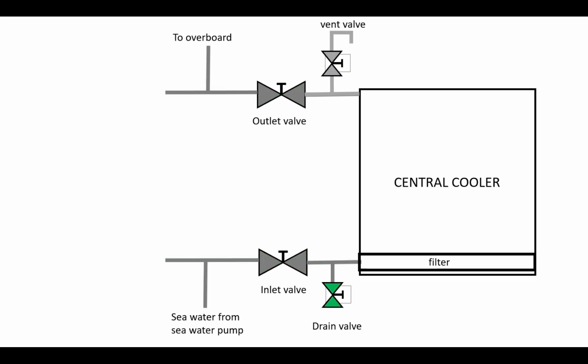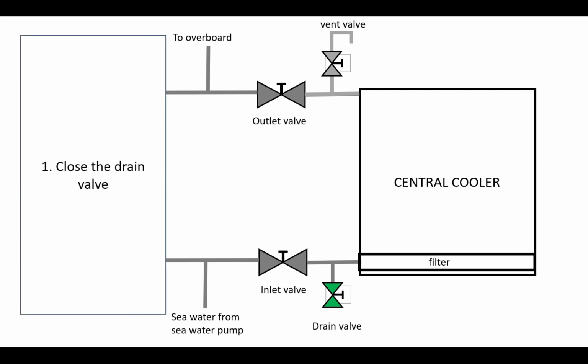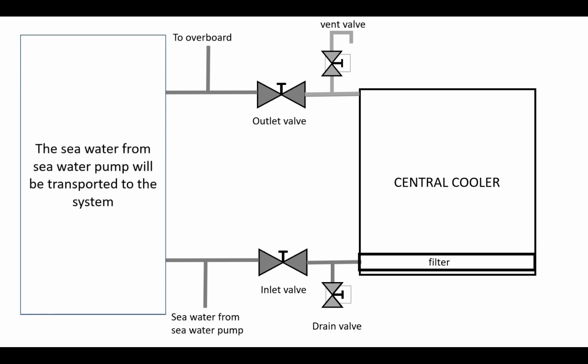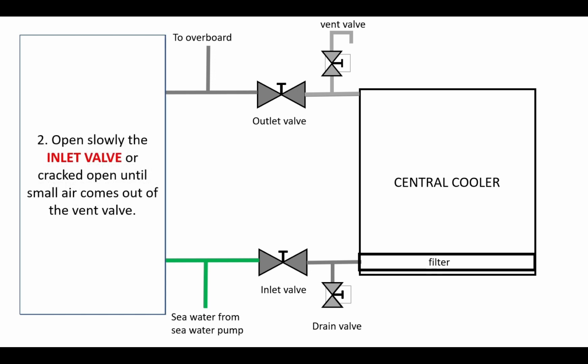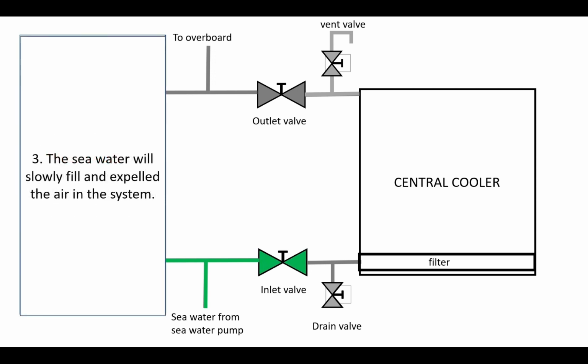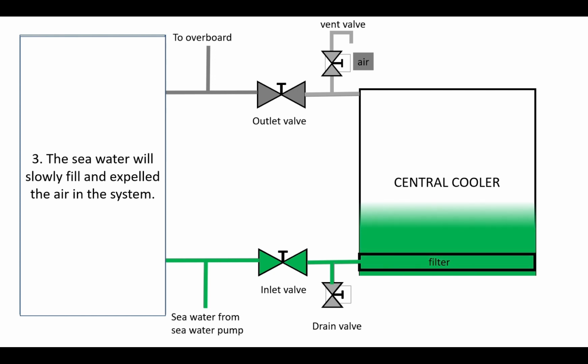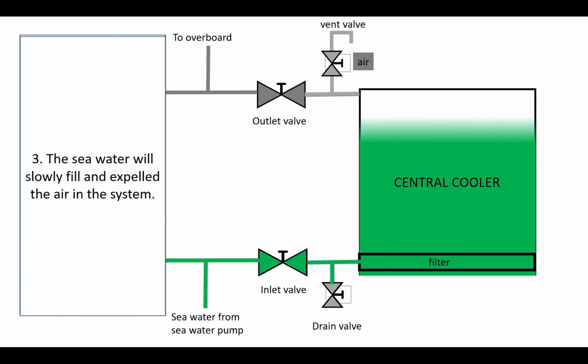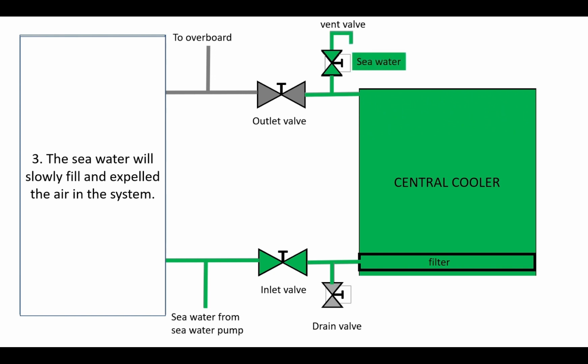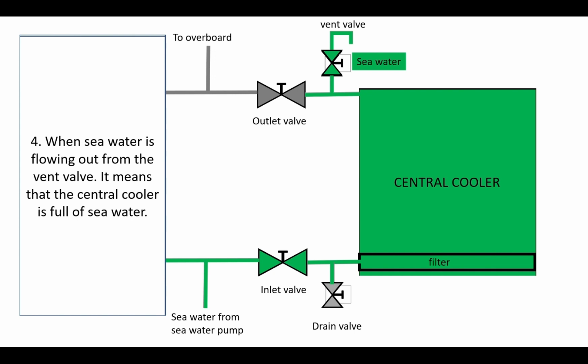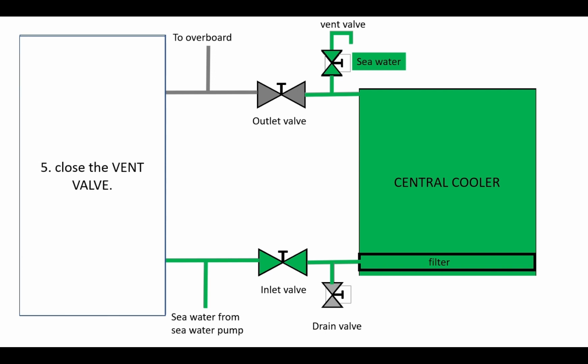Let's begin and fill the central cooler with seawater. First, close the drain valve. Seawater comes from the seawater pump. Second, open the inlet valve slowly, or crack it open, until air passes through the vent valve. The seawater will slowly fill and expel the air in the system. When seawater is flowing out from the vent valve, it means that the cooler is filled with seawater. Close the vent valve.